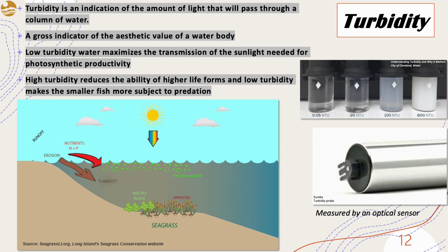In natural waters, turbidity is most often measured by an optical sensor, which measures the amount of light scattered by suspended particles at 90 degrees to a beam of infrared light. In very clear waters, little light is scattered and the turbidity reading is low. But in turbid waters, much light is scattered by suspended particles and the turbidity reading is high. The calibration of our turbidity probe is a 2-point calibration with air and a known concentration of formazine standard.